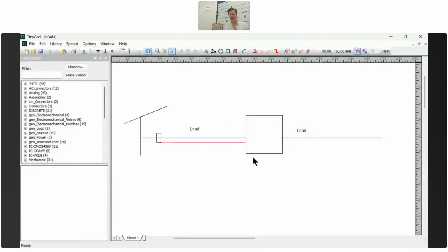But if you have it set to zero export to CT, then if you have a CT or a meter in the main switchboard and a load in between there and the inverter, then it will support the loads on the load side and on the grid side, which is probably for most load shifting hybrid residential city type applications is probably what you're going to do, because you might not even have this one connected at all. If the power hardly ever goes out, then you might not bother running the cable back. You're just going to have it all on this side, depending on what the customer wants.